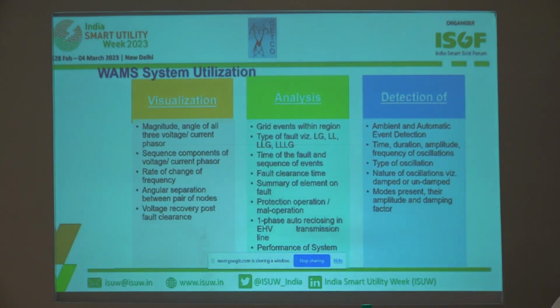We were detecting automatic ambient conditions, like any oscillations in the system. 2 or 3 times oscillation has been detected, once near Tarapur Atomic Power Station, and between Tarapur and Vapi we detected some oscillations. I have taken a screenshot of that, and that oscillation was saved. That oscillation has a good damping factor, so you can say that the Gujarat grid is in a stable condition.